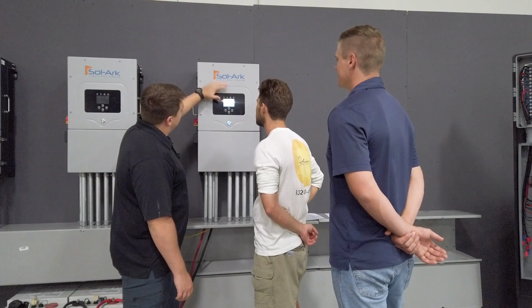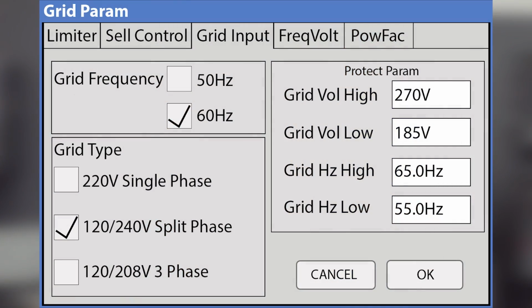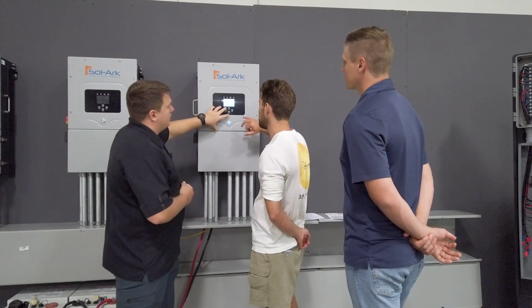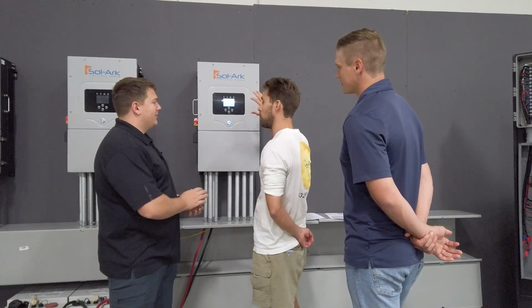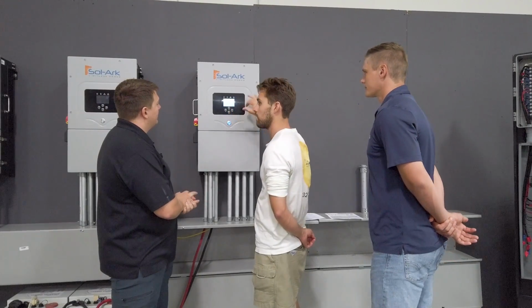So that's the sell control tab. Grid input, this again you're probably not going to need to edit. It defaults to 120/240 split phase, 60 Hertz, just like we have here in the States. If you do want to do a 3-phase install, this is where you would go to change your mode to 208 3-phase. One system can do 2 of the 3 phases, or you can bump it up to 3, 6 or 9, 12Ks to do balanced 3-phase sellback and backup. Real quick, we're about to do one of those with 3 12Ks. Yeah. So this is where we would come to do that.